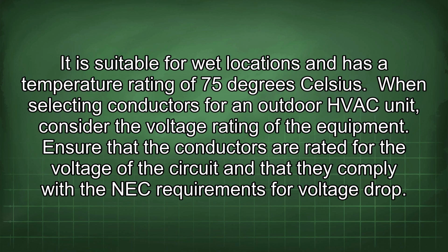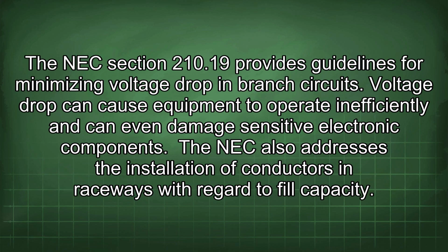When selecting conductors for an outdoor HVAC unit, consider the voltage rating of the equipment. Ensure that the conductors are rated for the voltage of the circuit and that they comply with the NEC requirements for voltage drop. The NEC section 210.19 provides guidelines for minimizing voltage drop in branch circuits. Voltage drop can cause equipment to operate inefficiently and can even damage sensitive electronic components.